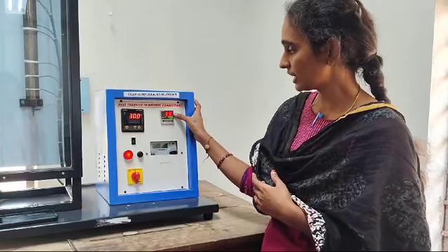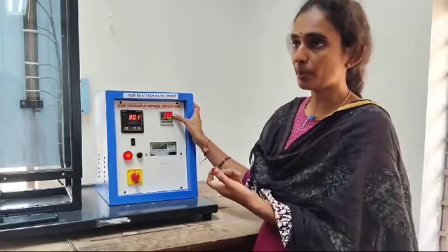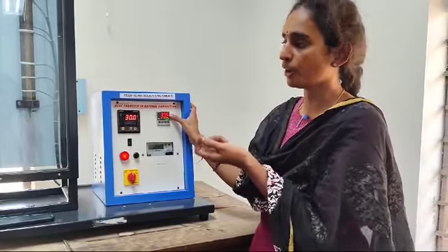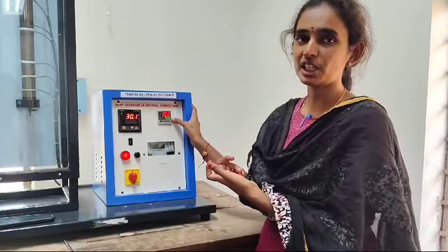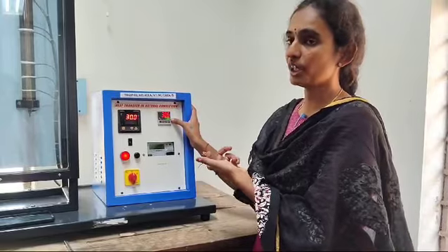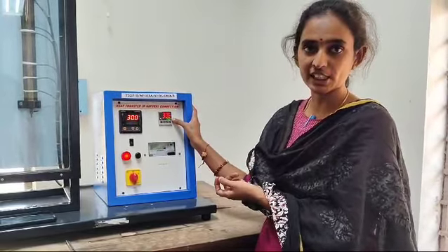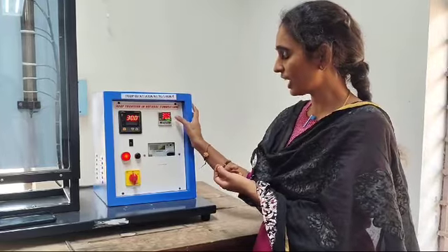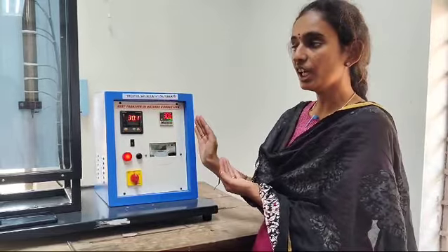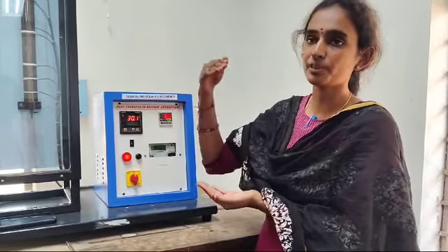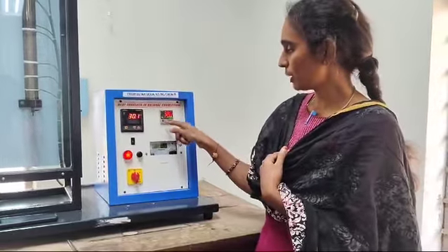The red color indicates the PV, that is the process variable, which means how much temperature there is at a particular point in time. The set value is a fixed value for the system. For this equipment we can fix it from 50 to 80 degrees centigrade. Here we fix the value at 70 degrees centigrade. So this is a fixed value, the maximum value input we will give to the system. Based on the input we are giving, we are going to calculate how heat is transferred from one end to the other end. So this is about the PID controller.